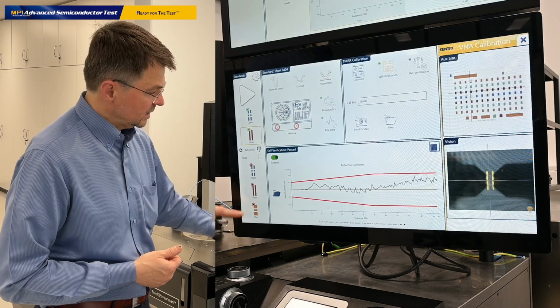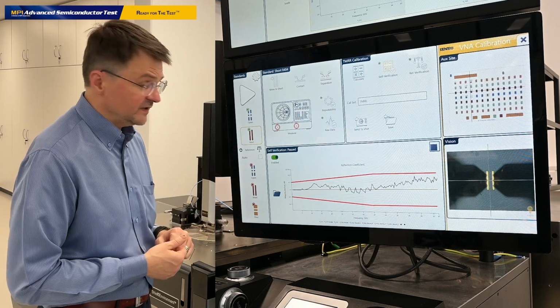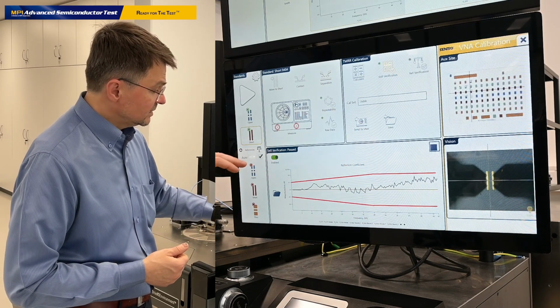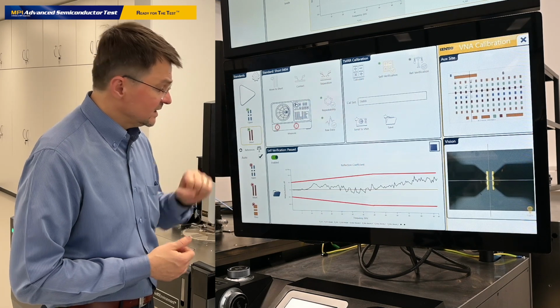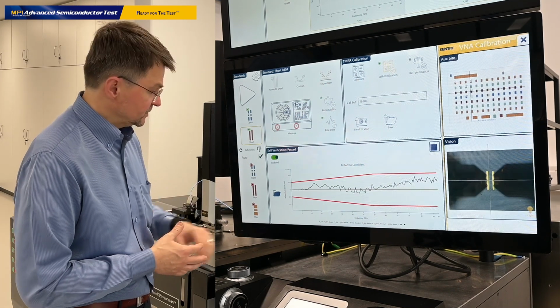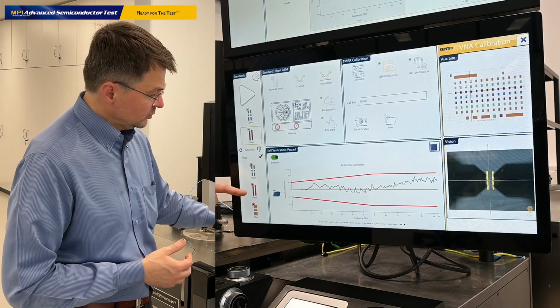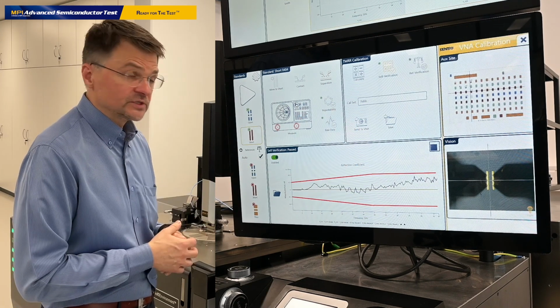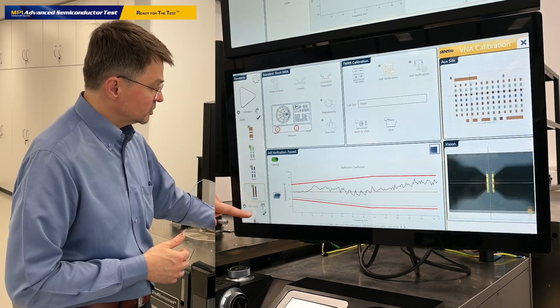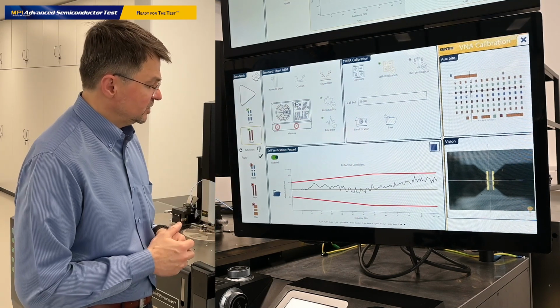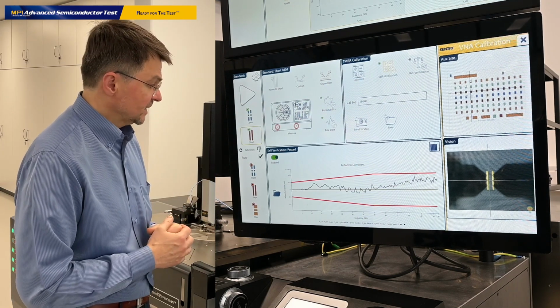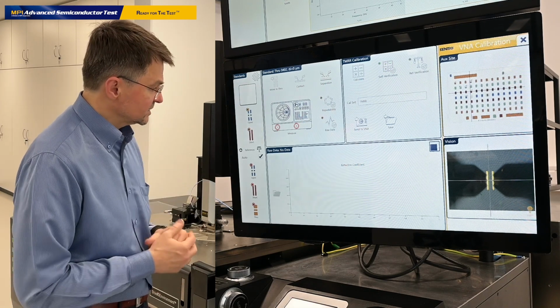verification list. So this is the list of the verification elements, and these elements can be measured right after we complete the calibration process. You see, we will go to the open, we will go to the short, and we will go to the through standard after we complete the measurements of the calibration standards and compute error terms. So let us see how it all works in action.